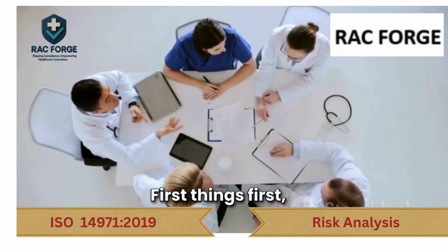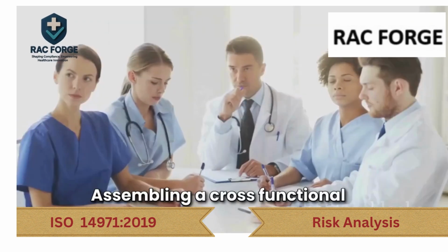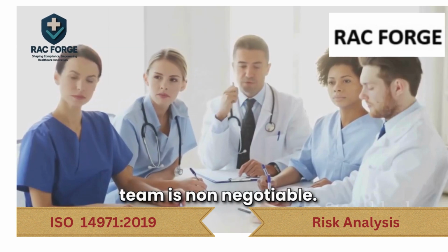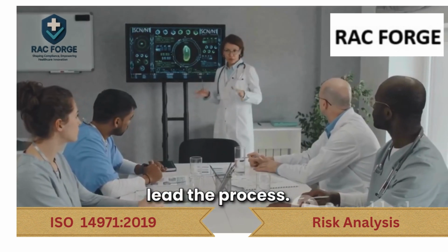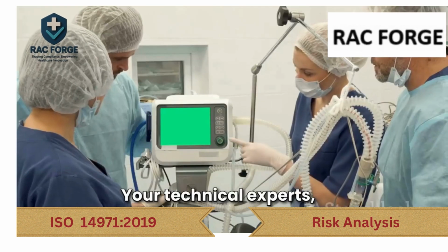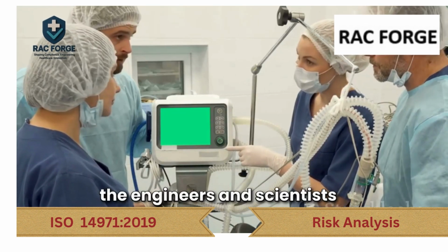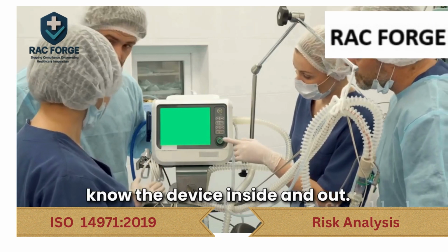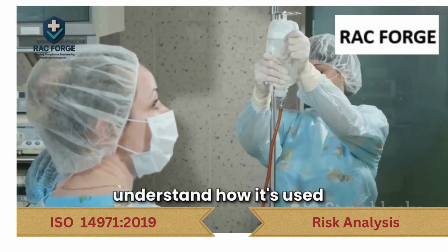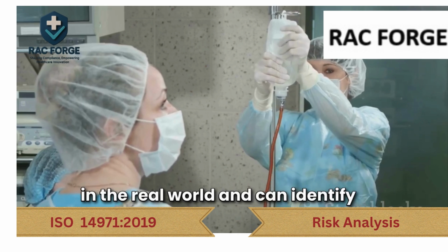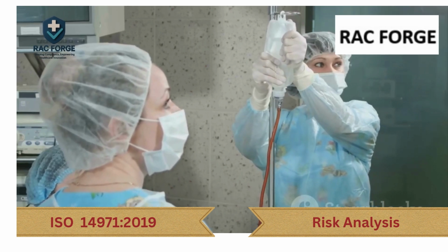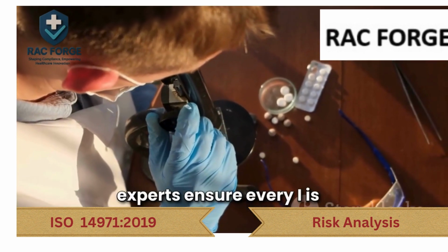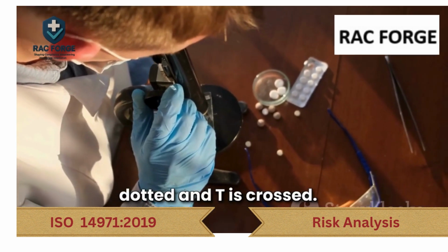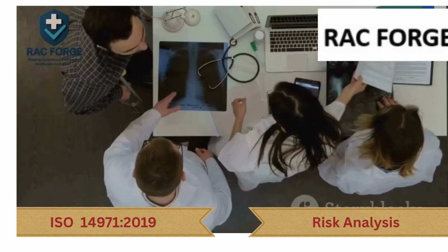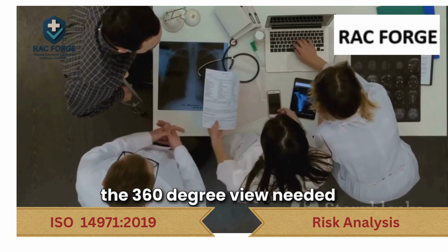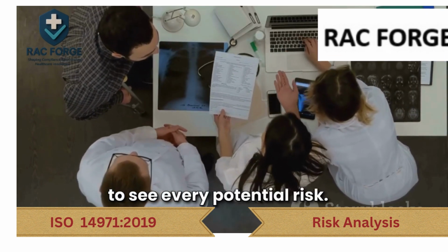First things first, you can't do this alone. Assembling a cross-functional team is non-negotiable. Your risk manager will lead the process. Your technical experts, the engineers and scientists, know the device inside and out. Your clinical specialists understand how it's used in the real world and can identify use-related hazards. And your quality and regulatory experts ensure every I is dotted and T is crossed. Together, this team has the 360-degree view needed to see every potential risk.